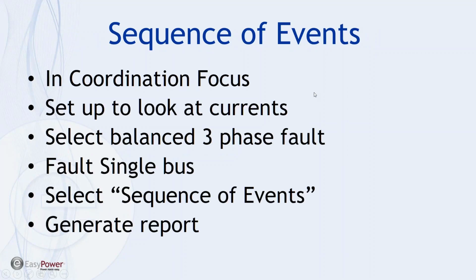I would like to reiterate how useful the sequence of events is. It's available in coordination focus. It's useful when we're looking at current, not incident energy. And if we select a three-phase bolted fault and fault a single bus, then the tool makes available the sequence of events icon, and looking at the report will give us an idea of where our weaknesses lie.